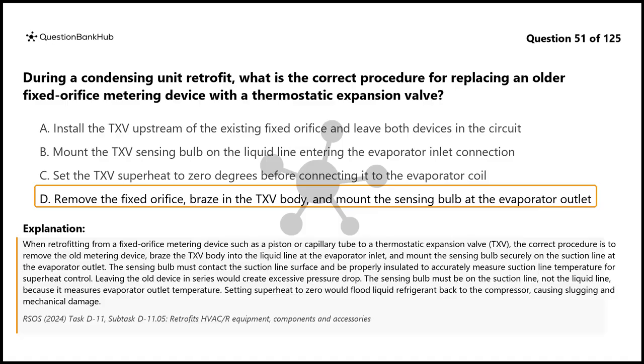The sensing bulb must contact the suction line surface and be properly insulated to accurately measure suction line temperature for superheat control. Leaving the old device in series would create excessive pressure drop. The sensing bulb must be on the suction line, not the liquid line, because it measures evaporator outlet temperature. Setting superheat to 0 would flood liquid refrigerant back to the compressor, causing slugging and mechanical damage.